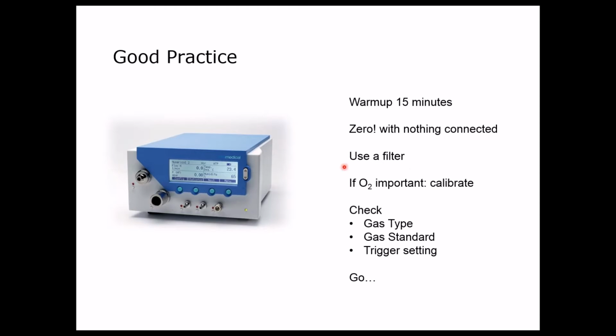If the O2 measurement we're doing is really important, then we should also calibrate the oxygen cell. I will show the calibration procedure later on during the practical part. O2 calibration should be repeated once every week, or daily if the oxygen measurement is really important. But usually once every week is sufficient.